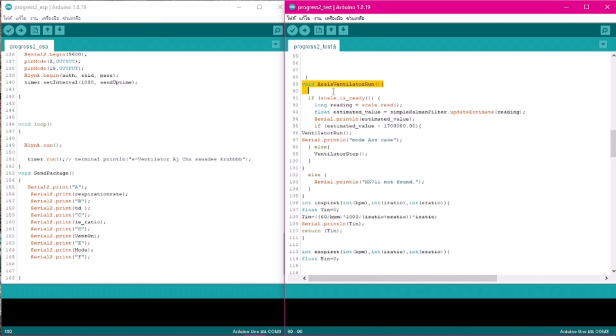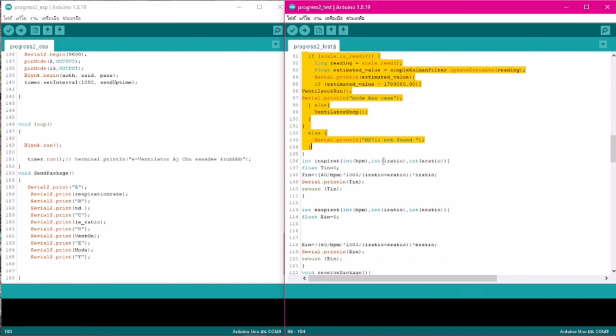In the function of assist mode, we use the pressure sensor that we connected before. If the estimate value that we get from the pressure sensor is less than 1,700,000, the ventilator will run. That means the patient tries to breathe in, and the ventilator is working to help the patient breathe. But if the estimate value is more than the value that we set, the ventilator will stop, so it will not reach the assist conditions.